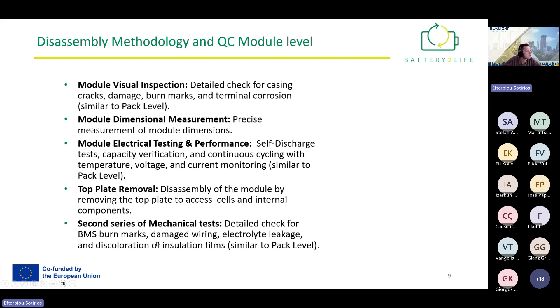Then we remove the top plate of the module to access the cell. We do a detailed check for BMS burn marks, damaged wiring, electrolyte leakage, which is very important, and discoloration in insulation films.